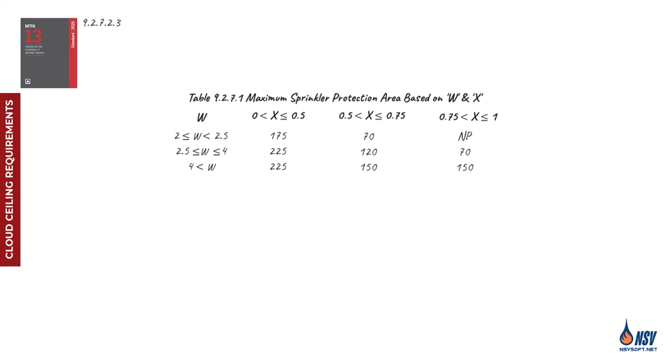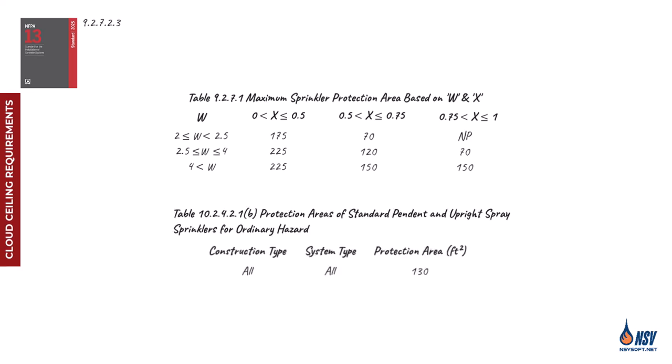For example, if the room we reviewed falls under the ordinary hazard occupancy classification, we must refer to Chapter 10 of NFPA 13 and use the maximum coverage area of 130 square feet, rather than the 225 square feet allowed by the cloud ceiling table.